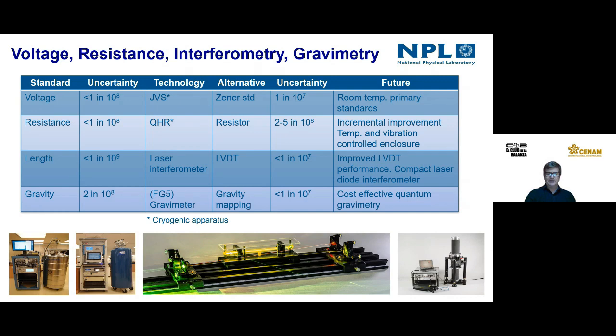Resistance we can improve by improving temperature control and reducing the thermal coefficient of resistors. We can use LVDTs instead of lasers potentially, at parts in 10 to the 7 level. And gravity, really, the only way to measure it at the level we need is using the commercial FG5 device — but people are looking at quantum gravimeters, a simplified way of measuring gravity and particularly changes in gravity, so there is work going ahead to simplify that too.